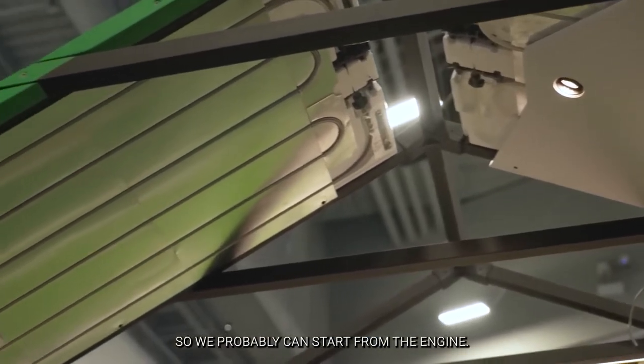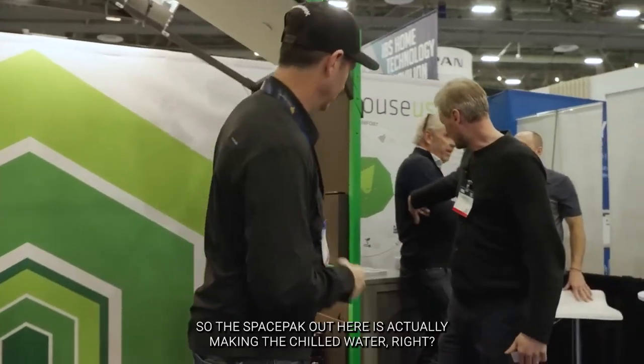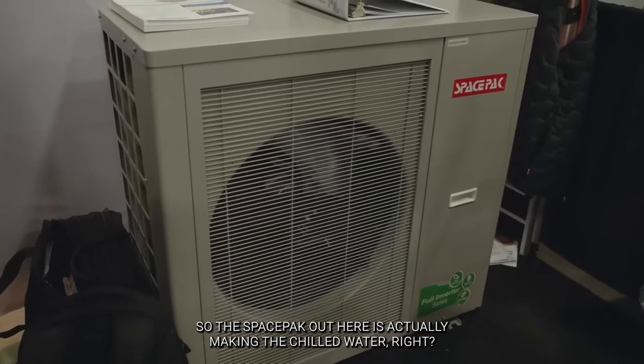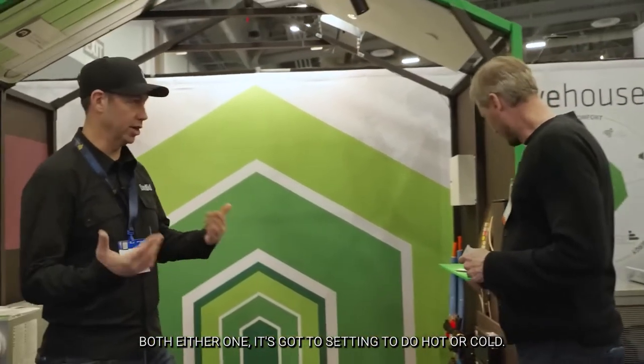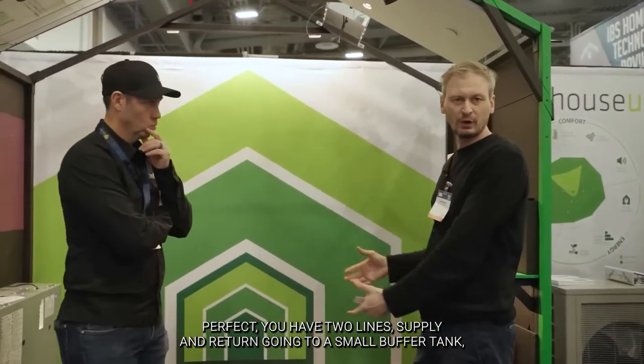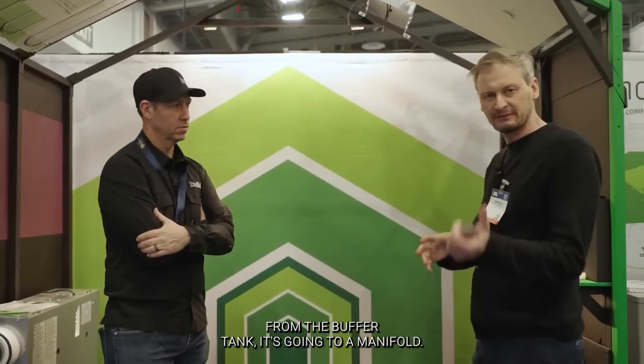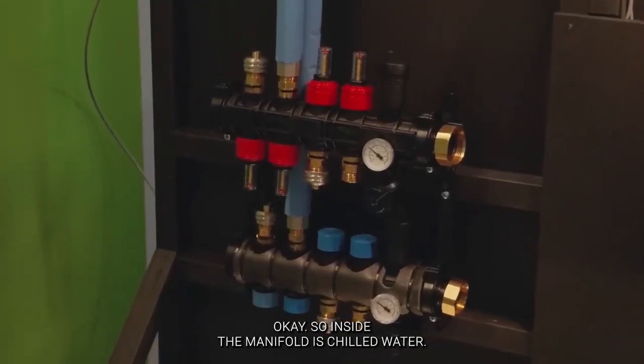We can start from the engine. The SpacePak out here is actually making the chilled water. The heat pump produces both hot water and chilled water — you set it to hot or cold. You have two lines, supply and return, going to a small buffer tank, and from the buffer tank it goes to a manifold. Inside the manifold is chilled water.